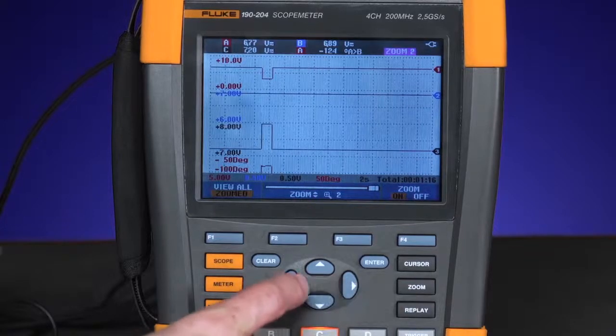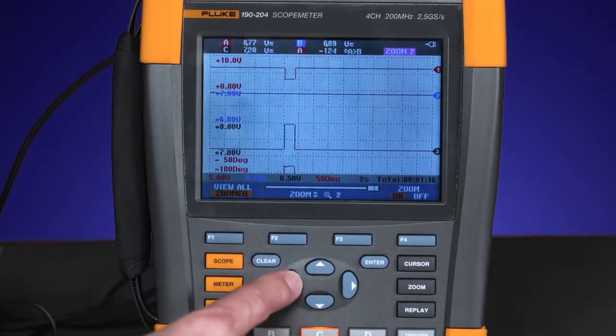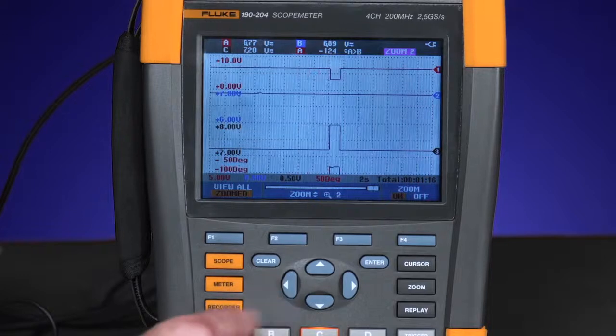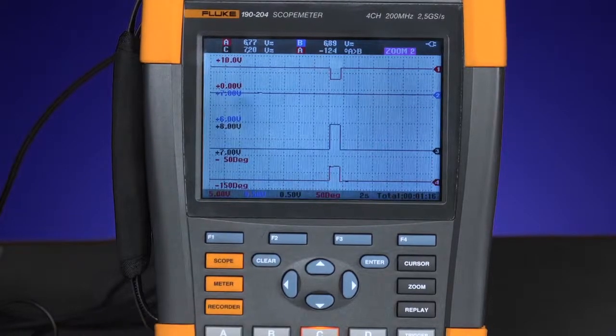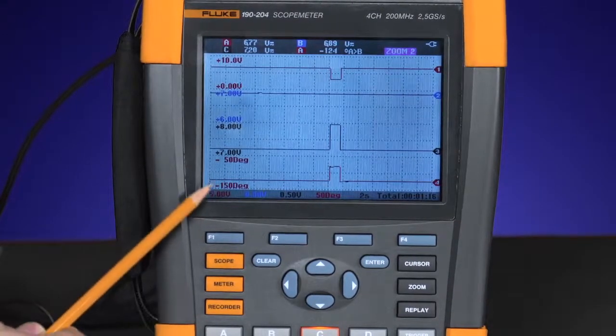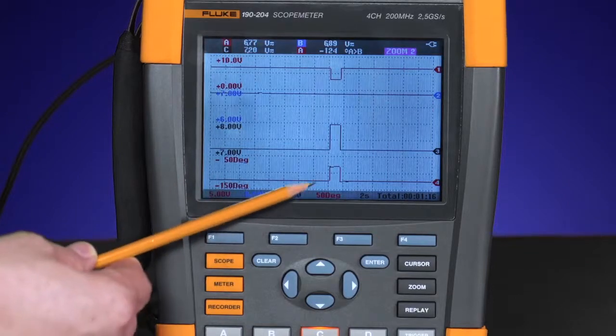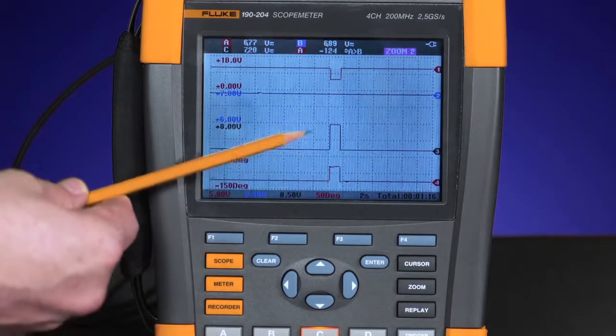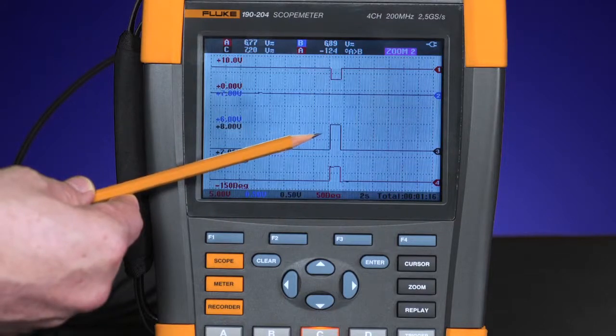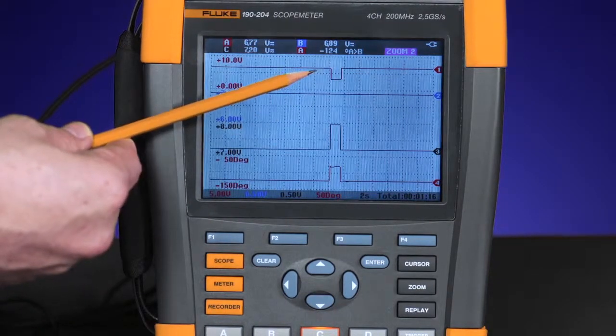Zoom in to look for the signal of interest. Here you can see how the oscilloscope has captured a phase angle change between phase A and B, and you can see the corresponding change in the amplitudes of input A and B.